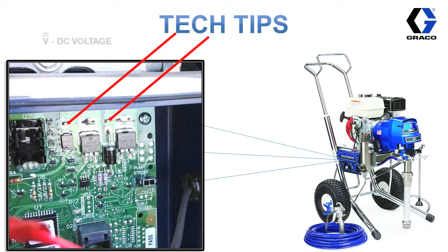Okay. And what are you looking for there? And then again, if it's not where it's supposed to be, how do you fix this? If you disconnect the pressure switch and the display board and you're still not getting the proper voltage, then we've got a bad board. If you disconnect those two parts and we are getting proper voltage, either your display board's got a short, so it's taking away all the DC voltage, or your pressure switch has also got a short and is taking away all the voltage. So would you be replacing both of those parts, or one or the other, and how would you know which one? Just plug one in at a time, and whichever one takes away your power, that would be your bad part. So it's kind of a process of elimination there too. Correct. Okay.